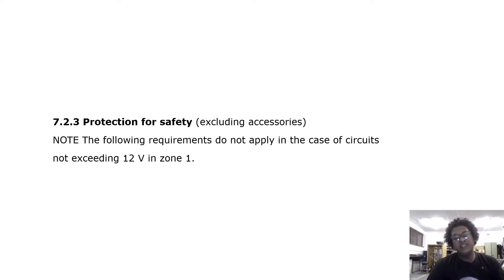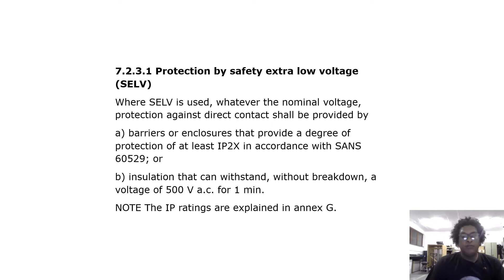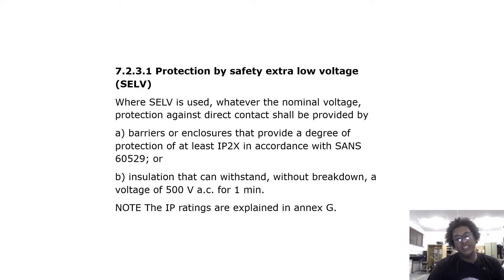Regarding protection for safety — note the following requirements do not apply in the case of circuits not exceeding 12 volts in zone 1. Where safety extra low voltage (SELV) is used, whatever the nominal voltage, protection against direct contact shall be provided by barriers or enclosures that provide a degree of protection of at least IP2X in accordance with SANS 60529, or insulation that can withstand without breakdown a voltage of 500 volts AC for one minute. The IP ratings are explained in Annexure G.